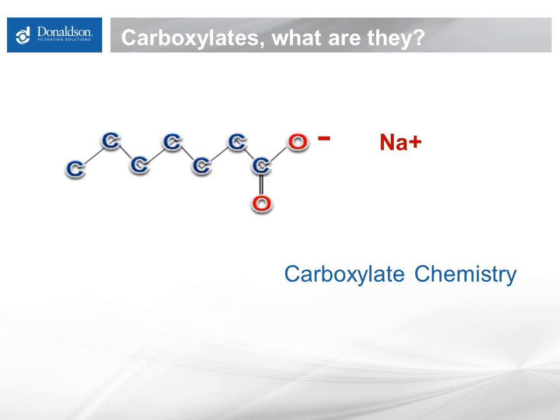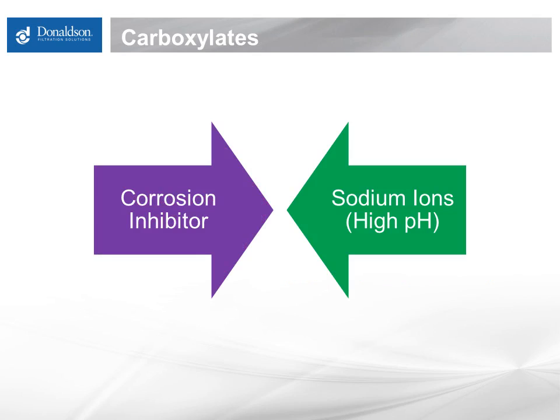This compound is more stable if it can take an electron from something else in the fuel. Commonly, in the formation of carboxylates, that would be an alkali metal — a group of metals on the periodic table that donate their electron. This includes sodium or potassium, which can be found in diesel fuel. Certain refinery processes or tank bottoms water also contain sodium and can contribute that sodium ion. The carboxylates we are talking about today are highly fuel-insoluble materials, meaning once they are formed, they will not re-dissolve into the fuel.